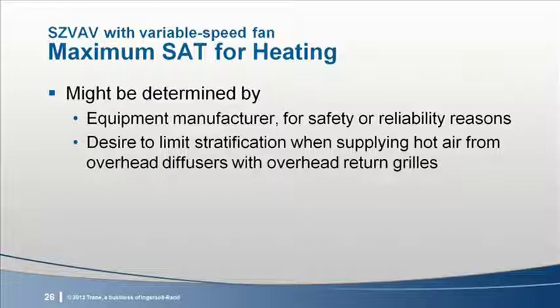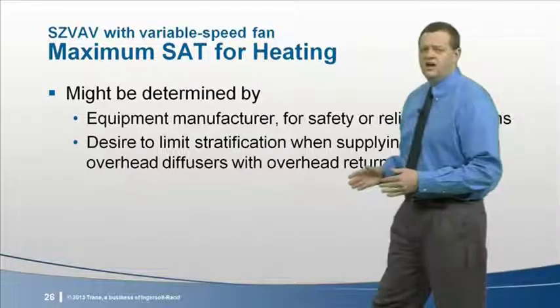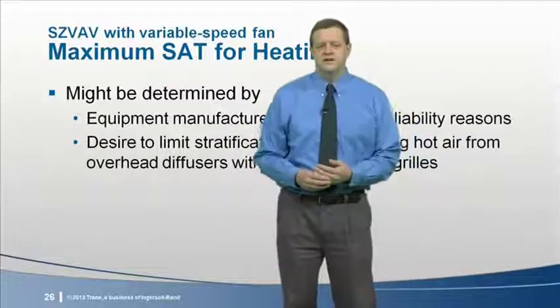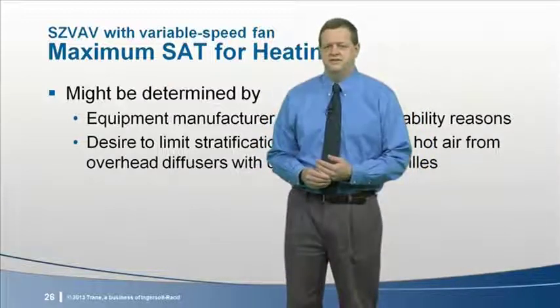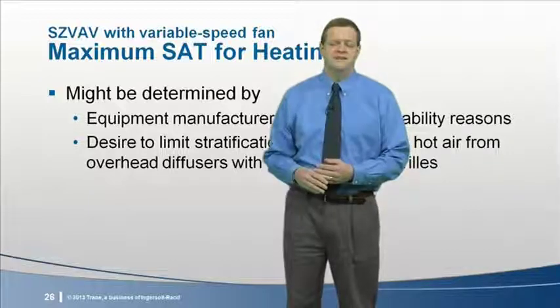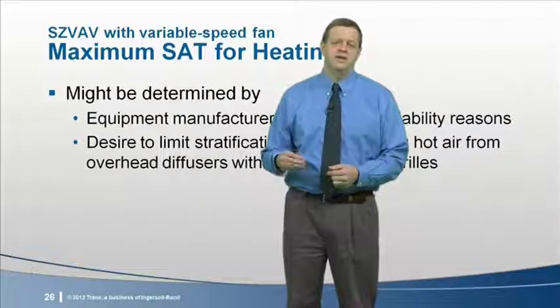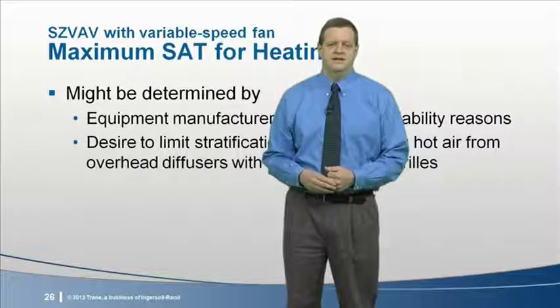Or for some applications, this temperature might be limited to minimize stratification when supplying hot air from overhead diffusers. When both supply diffusers and return grills are mounted in the ceiling and the supply air is hot, the buoyancy of this hot air will tend to cause some of it to stay up near the ceiling and bypass from the supply diffusers to the return grills. This can cause comfort problems, and as we discussed during our last E&L program in ASHRAE Standard 62, this bypass air impacts ventilation performance and requires bringing in more outdoor air through the system intake.